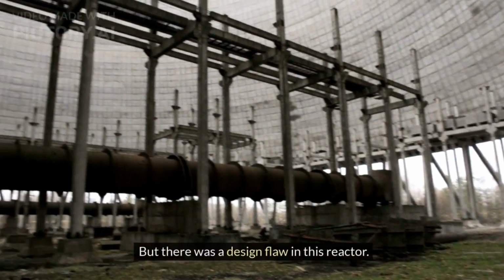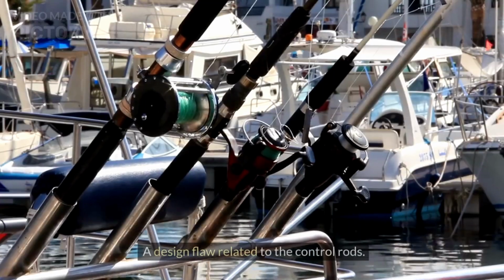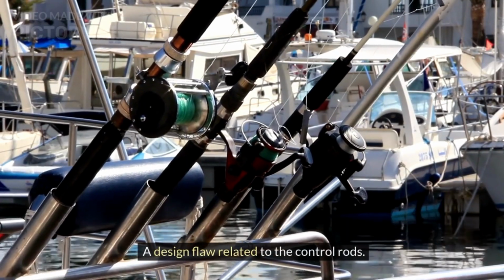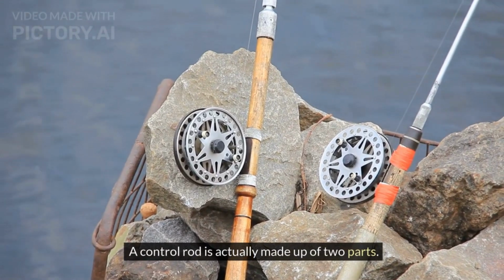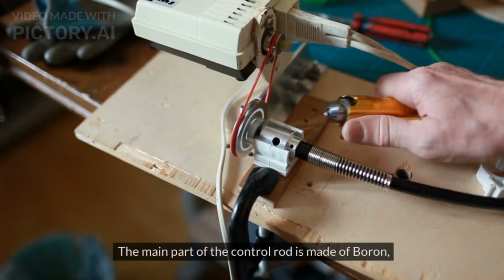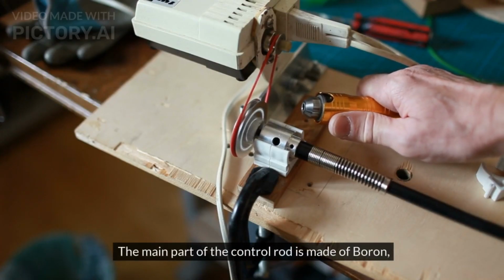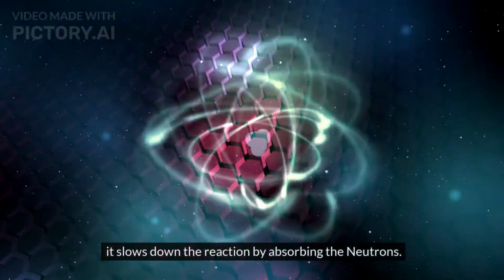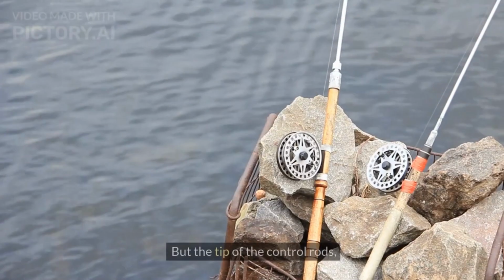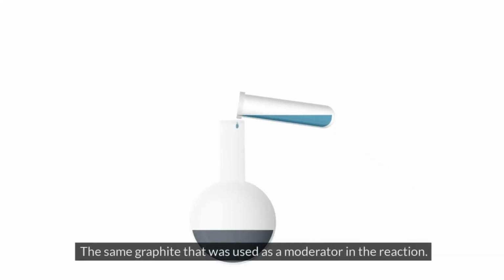But there was a design flaw in this reactor. A design flaw related to the control rods. A control rod is actually made up of two parts. The main part of the control rod is made of boron. It slows down the reaction by absorbing the neutrons. But the tip of the control rods were made of graphite. The same graphite that was used as a moderator in the reaction.